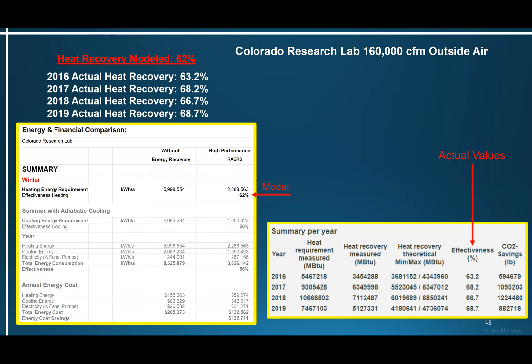Another system — a research lab in Colorado with 160,000 CFM of outside air. The model calculated 62% annual heating effectiveness. Actual post-occupancy results: 2016 — 63.2%, 2017 — 68.2%, 2018 — 66.7%, and 2019 — 68.7%. Again, pretty close.